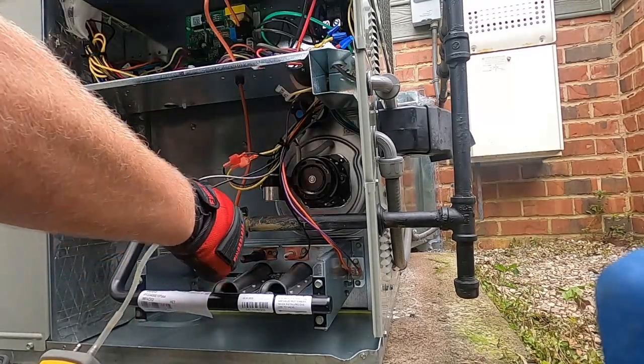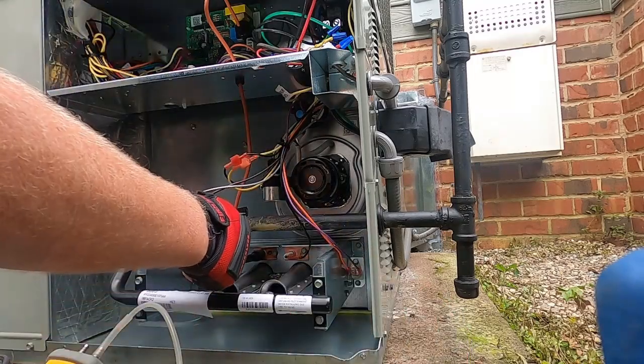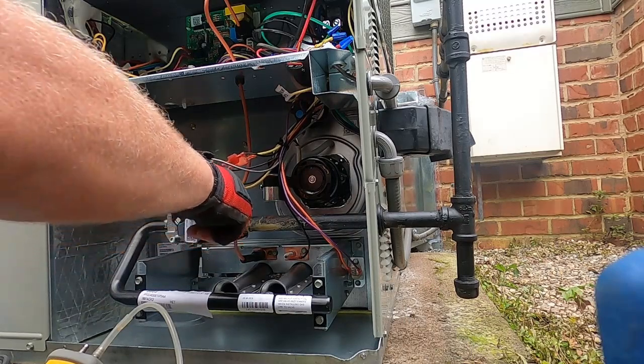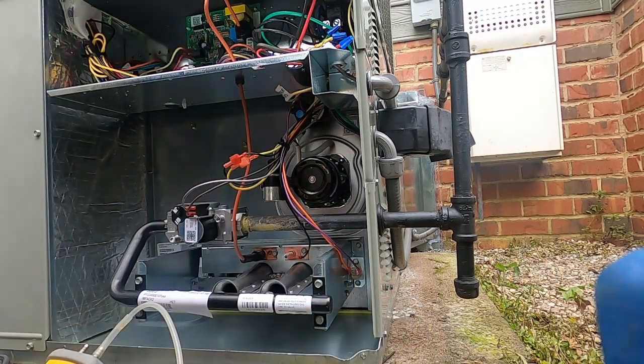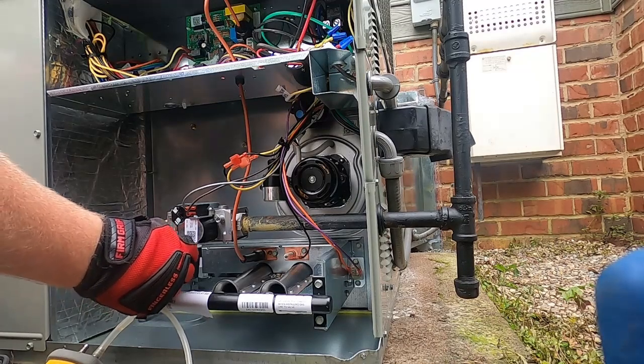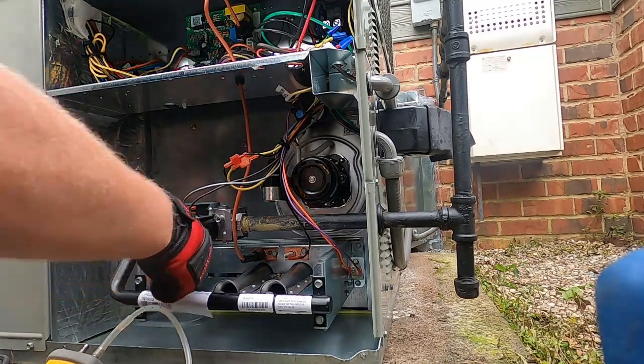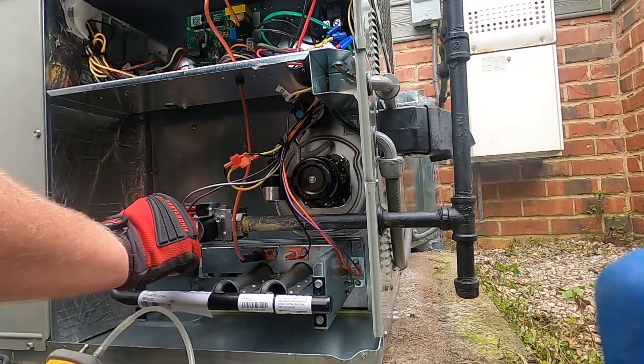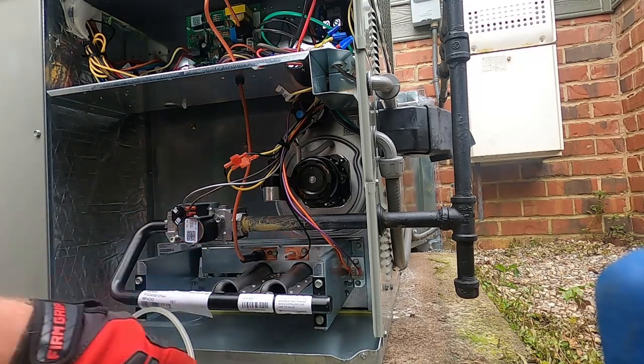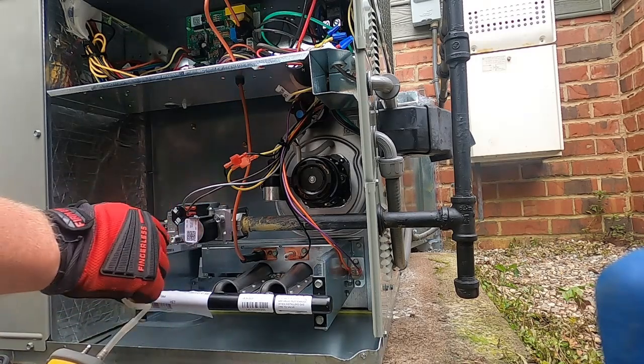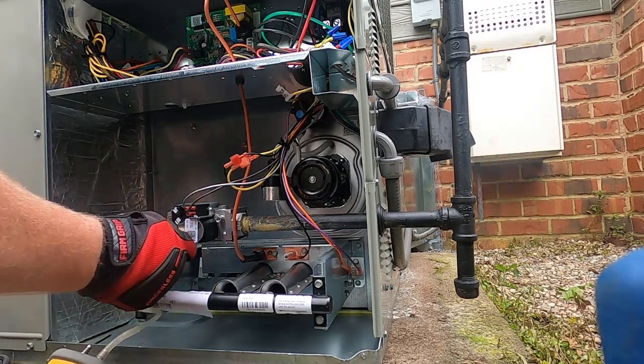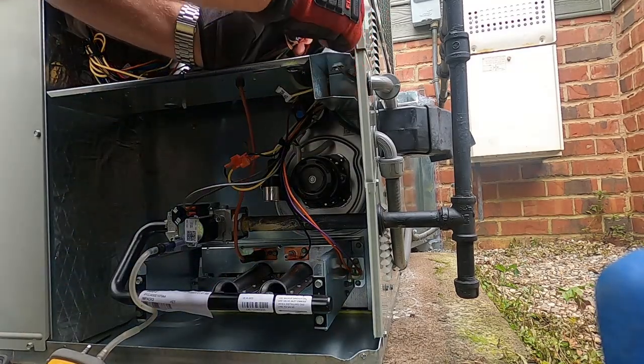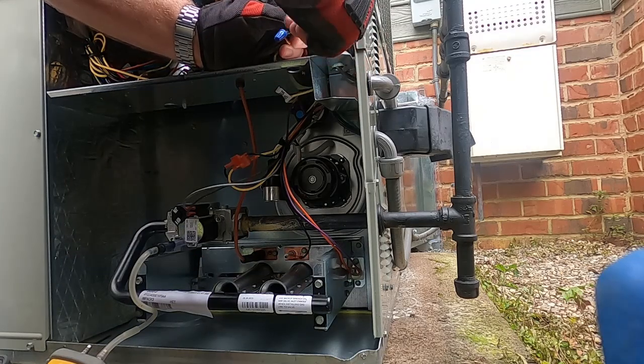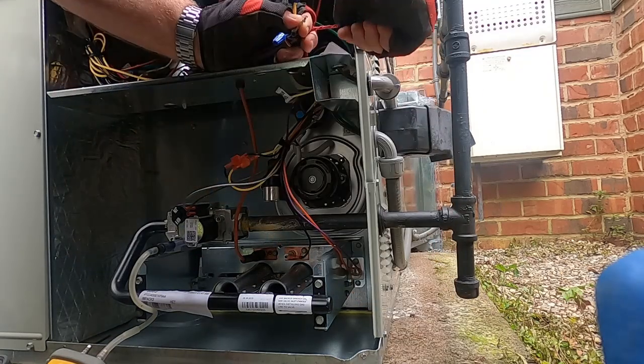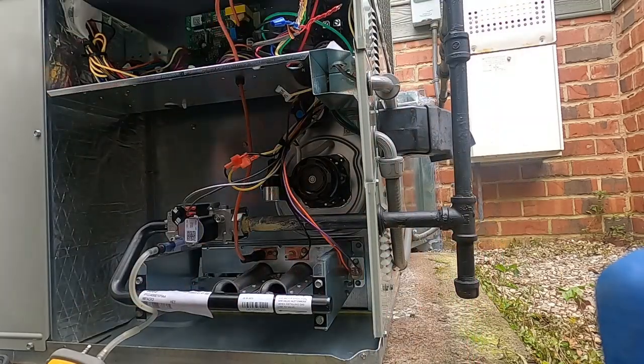So now I can turn this thing on, get the inlet gas pressure set on it. Temperature rise on it. And you only have to crack these. You don't have to pull these fittings all the way out. So zero my manometer. And I'm just going to simply come up here. Jump it out.